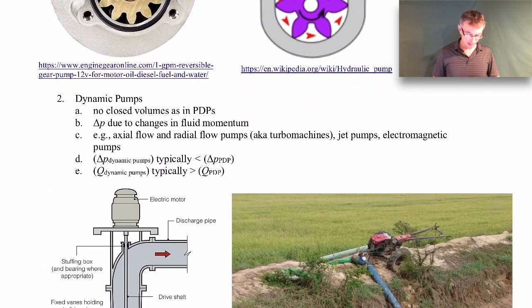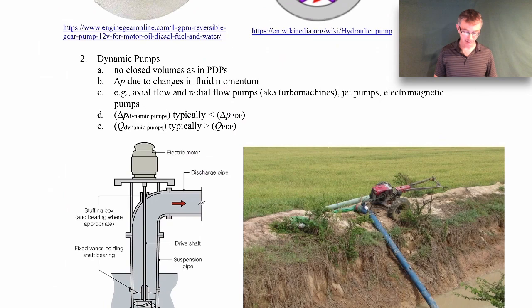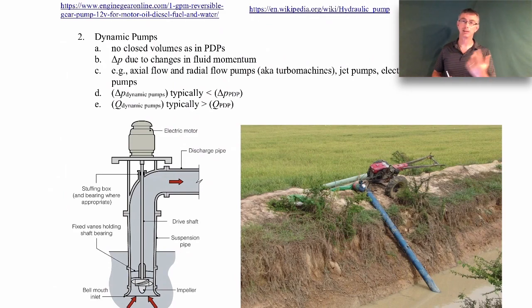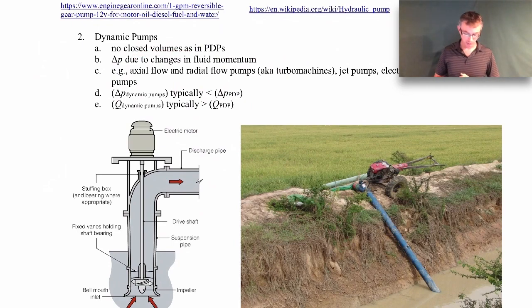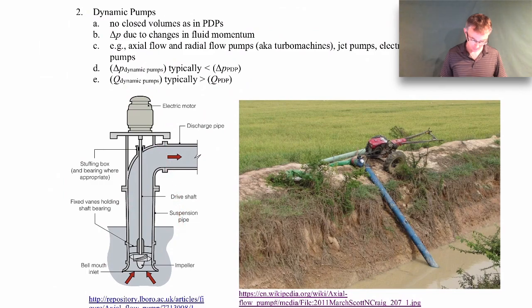Instead we'll focus primarily on dynamic pumps. A centrifugal pump is an example — dynamic pumps rely on changes in fluid momentum to produce the pressure rise. You spin the fluid up to high speed with a lot of kinetic energy and momentum, and that gets converted into pressure as it slows. There are no closed volumes in dynamic pumps as there were in positive displacement pumps. Examples of dynamic pumps include axial flow and radial flow pumps. A radial flow pump is the centrifugal pump; an axial flow pump has flow going in the same direction throughout.